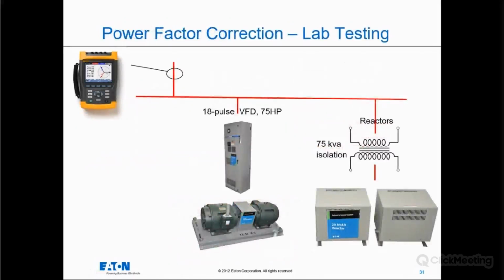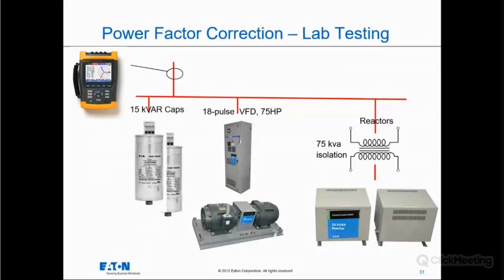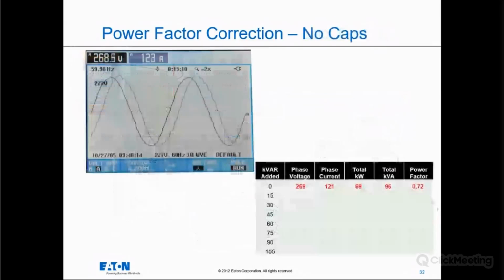In our power quality labs, which we operate two in the United States, one in Houston and one in Pittsburgh area, we actually have real loads that we can hook up, capacitors, inductors, all kinds of our power quality equipment, and see what it does in the real world with real loads operating. So in our lab, we actually set up an example where we had a motor running and we're adding capacitors, so we could see what that looks like in terms of waveform and real numbers.